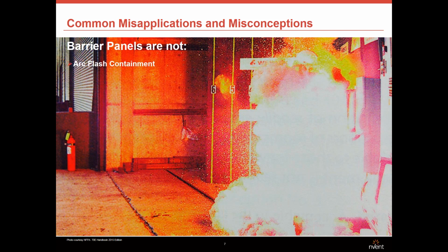A barrier panel is considered an arc flash prevention method, preventing incidental contact with live electrical connections in an area beyond the panel. It will not contain an arc blast in the case of an arc flash incident. So I just want to be absolutely clear that it is not containment.